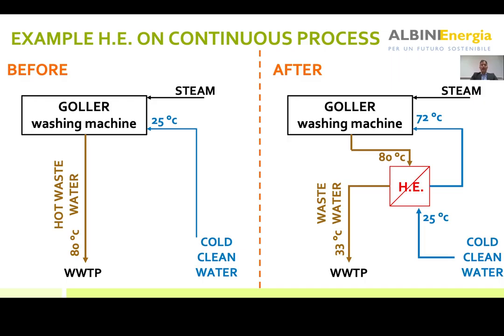This slide shows a washing machine which is a continuous machine. A continuous machine is a machine that requires fresh water at the same moment it is discharging wastewater. So you don't need to collect the fresh water and the wastewater - you can go directly to the wastewater heat exchanger. In this case, it's very easy to apply.